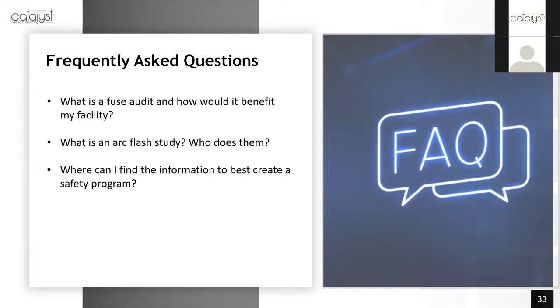So what a fuse audit is — when you go into an industrial facility into a storage crib or materials storage area, what we typically find is a lot of duplicate fuses from three or four different manufacturers. What a fuse audit does is it allows us to provide the end user with a report indicating what they have in stock and allowing us to reduce that inventory. When we do the fuse audit, we identify any fuses that could be potential arc flash hazards — whether it be a fuse with a low interrupting rating or a renewable fuse that could be upgraded with a safer product — and we indicate what that safer product is. It's a free service that we provide at Littelfuse, allowing us to identify hazardous fuses and provide a recommended upgrade.